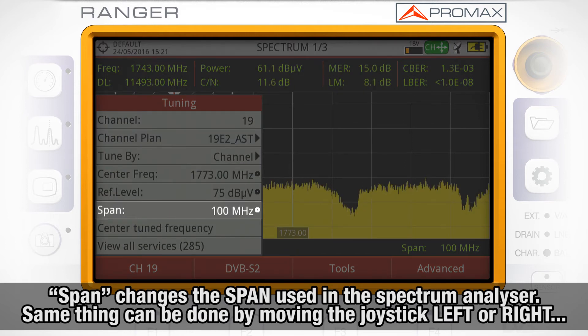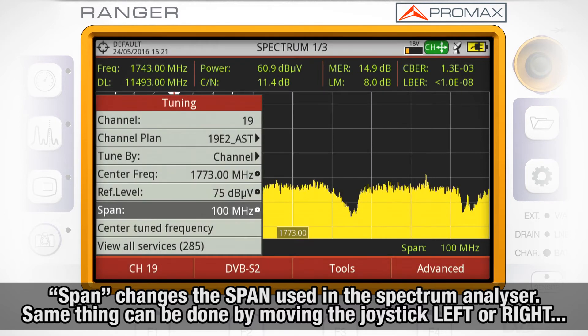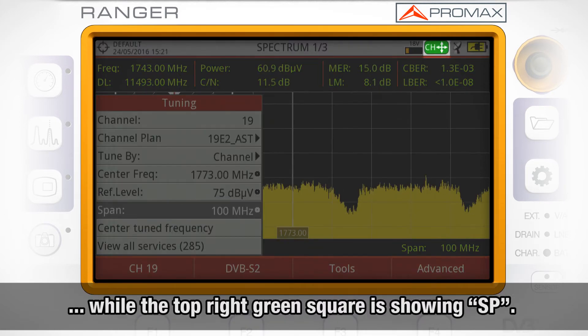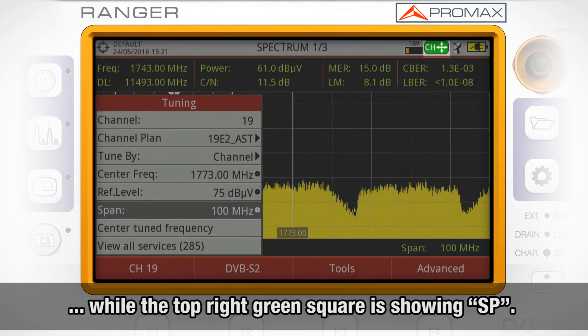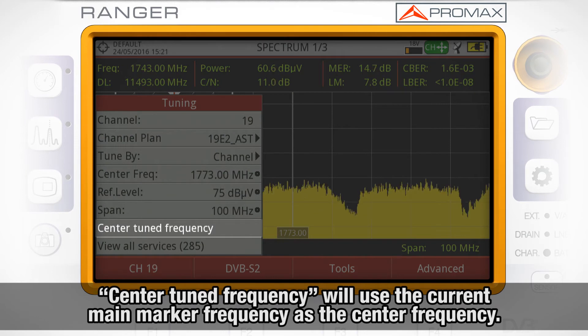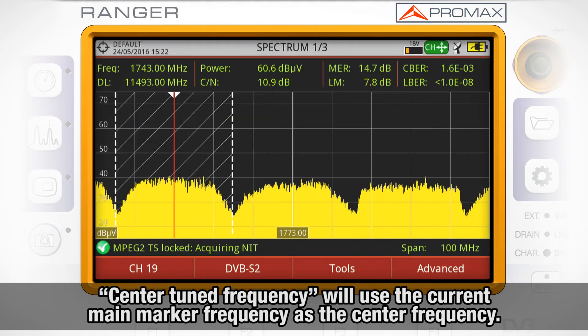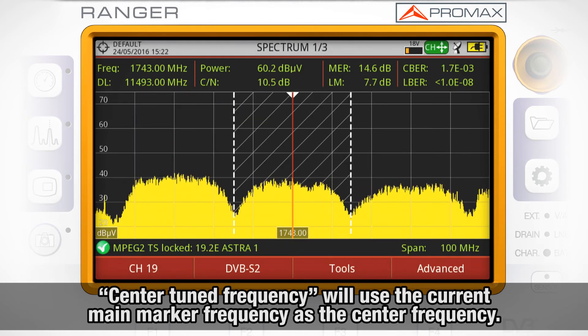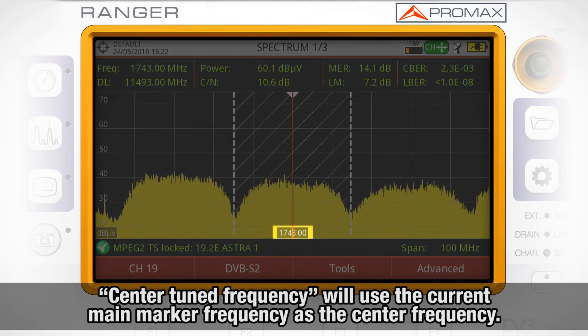Span will change the span used in the spectrum analyzer. The same thing can be done by moving the joystick left or right while the top right green square is showing SP. Finally, center tuned frequency will use the current main marker frequency as the center frequency, so the main marker will appear now in the center of the screen.